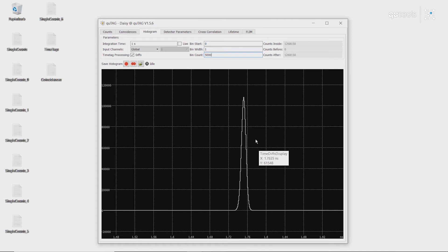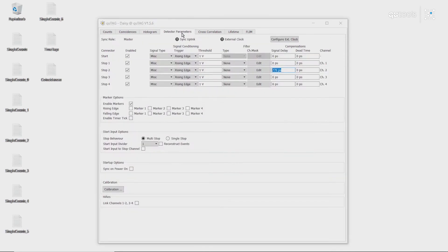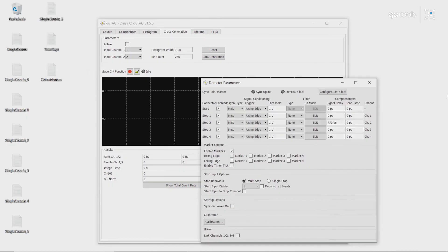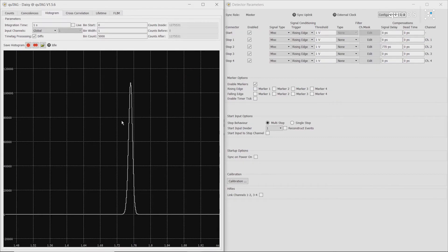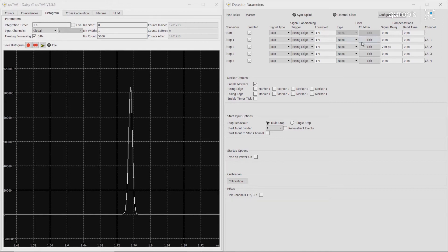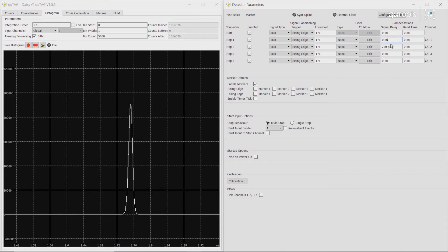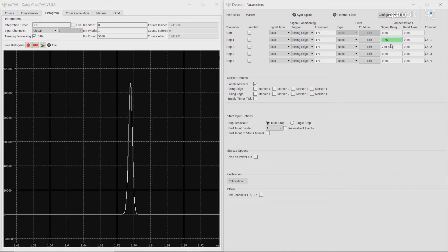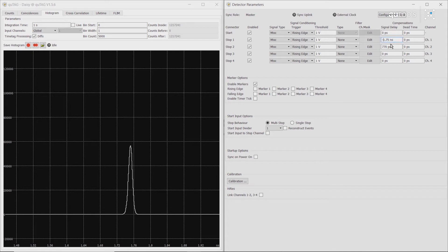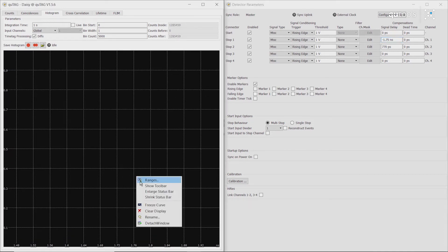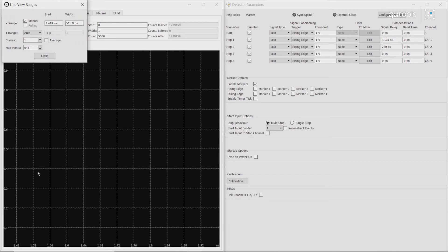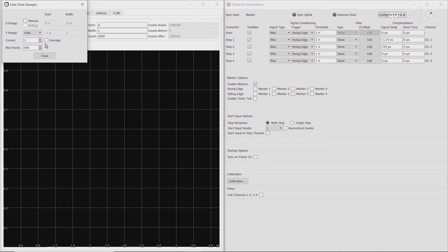If we wanted to correct for this, we can simply go to detector parameters and adjust the signal delay of channel 1 to the negative of that number. So 1.75 nanoseconds. As we can see, we no longer have any values at that range.